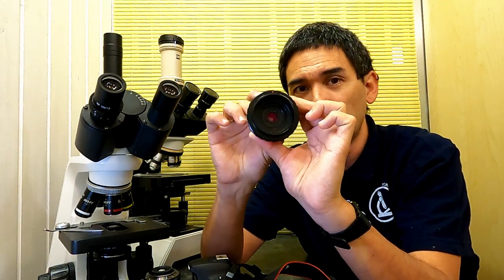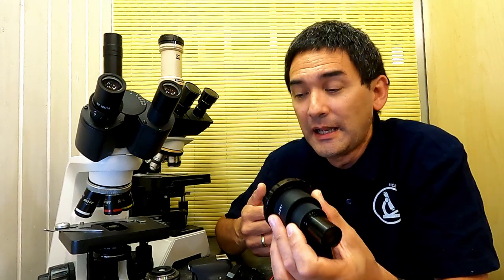It's just going to make the field of view smaller, but it doesn't do anything else. I'm kind of getting ahead of myself. So this is basically a problem. And the second problem is, not only does this have no function in other words, and the second problem is, and that's even worse, it's not parfocal. So this basically means that when I connect the camera, it's so out of focus that it's not even usable. You have to refocus so much that, forget it. So essentially I have no use for this adapter.